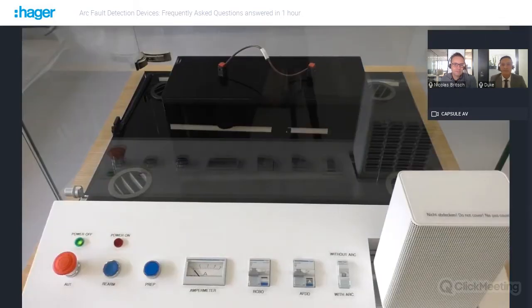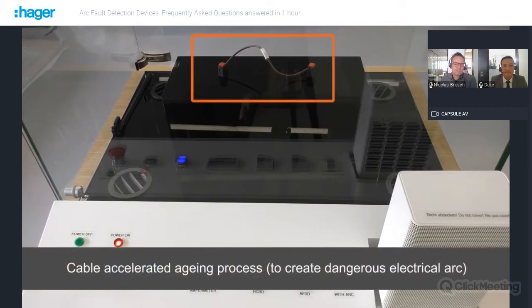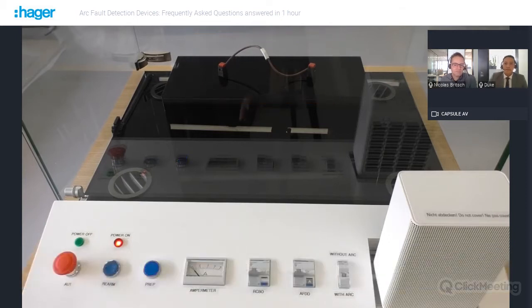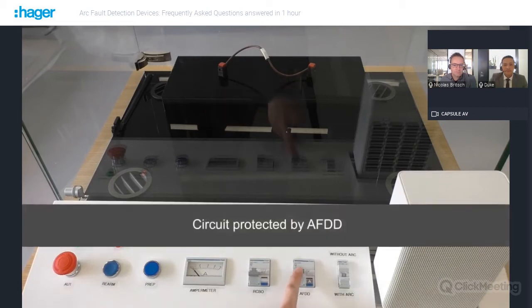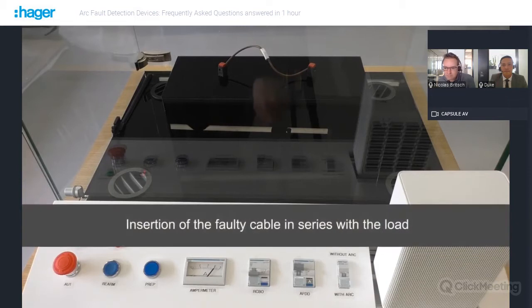So the wire has been put in the tester, and now we are ready to start the cable accelerated aging process. As described in the standard, we use high voltage in order to create a carbonized path. You can see some smoke coming out of the cable as high voltage has been applied. So here we will demonstrate the difference between an RCBO and an AFDD. First we will start with the AFDD, which will energize the circuit without any fault. The appliance, which is an electrical heater, on the right is powered on. And now we will insert the faulty cable in the circuit by switching the interrupter on the right.